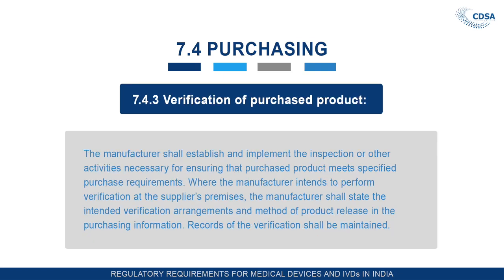Verification of purchased product. This is basically, in common terms, testing of the raw materials purchased. But in medical devices, it may well go beyond the verification that is required for drugs. The manufacturer shall establish and implement the inspection or other activities necessary for ensuring that purchased product meets specified purchase requirements. You may have to visit the vendor's premises to inspect it or carry out anything else to ensure that the purchased product meets the specified purchase requirements.